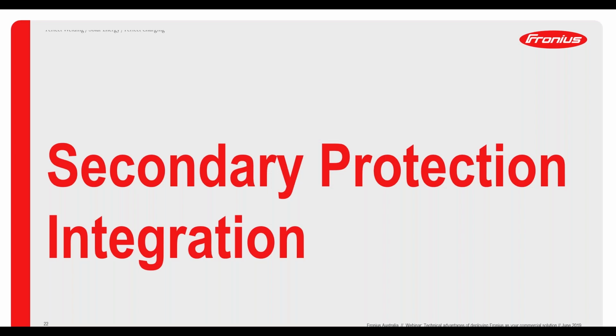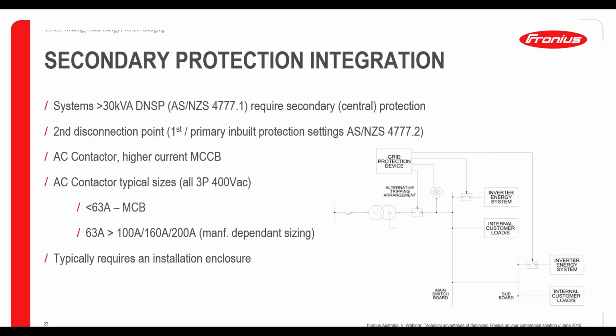One important thing with commercial deployment of Fronius, especially big inverters, ECOs in this case, is the secondary protection requirement and integration. As you may be aware, all systems in Australia above 30 kVA rating from the local network, as well as the AS/NZS 4777 requirement, will say that there's a central protection requirement that has to be included in the system. That typically would be a second disconnection point for the generation equipment. You can see a small graph on the right side here showing a typical grid protection device or relay that senses what's going on with the grid, the LV side of things, and then decides to connect or disconnect the inverter generation devices or the inverters.